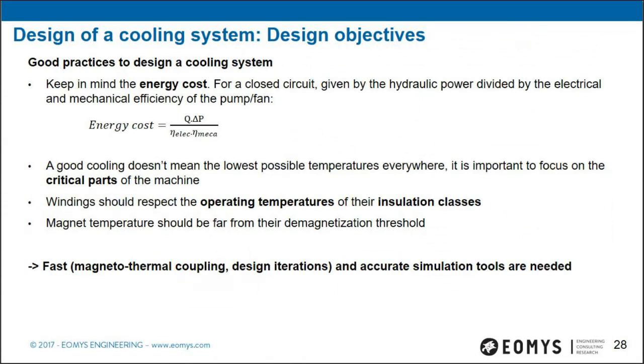Other good practices for cooling system design: always keep the energy cost of the solution in mind. If you improve machine efficiency but the cooling energy cost is high, the balance must be found — the energy cost for a closed circuit is hydraulic power divided by both pump mechanical efficiency and electrical efficiency. A good cooling system does not mean the lowest possible temperatures everywhere, but focuses on critical parts: windings should respect insulation class operating temperatures with a safety margin of about 10 degrees, and magnet temperature should be kept well below the demagnetization threshold.